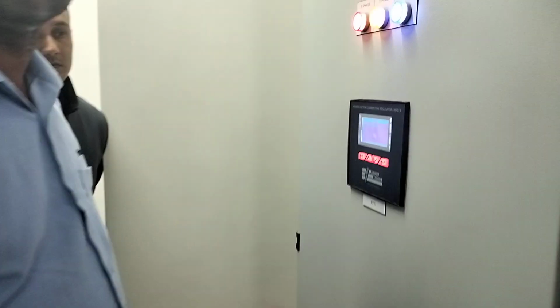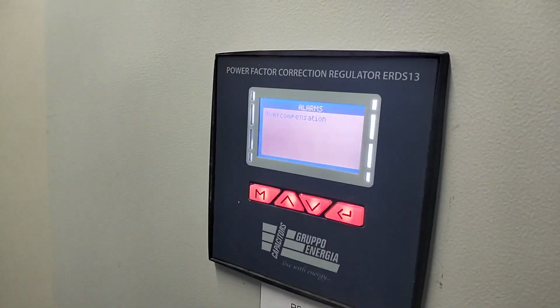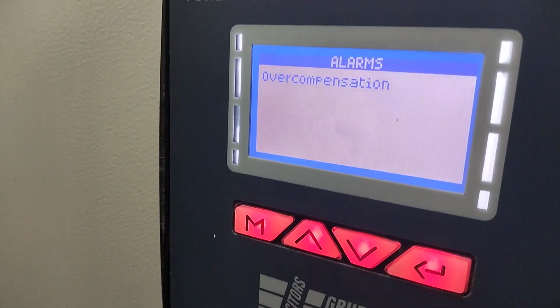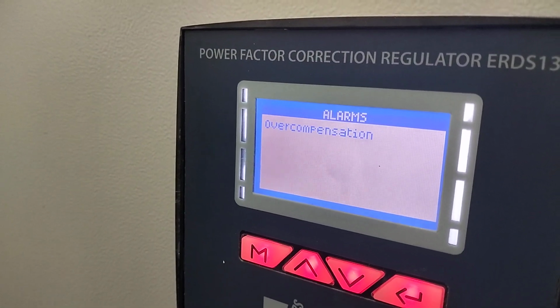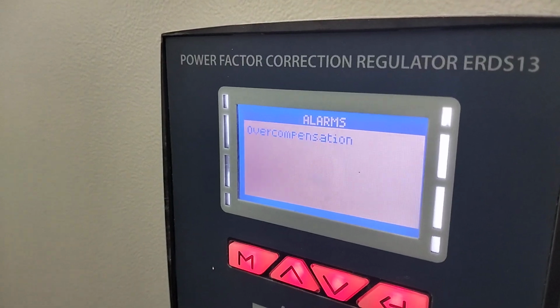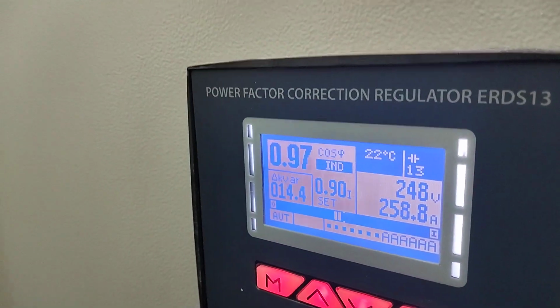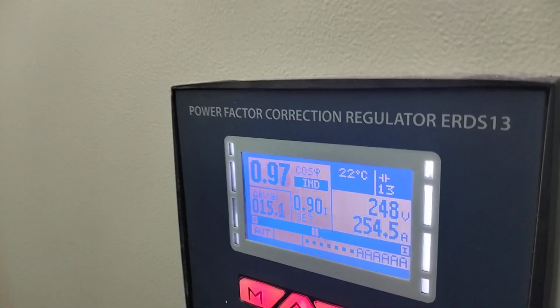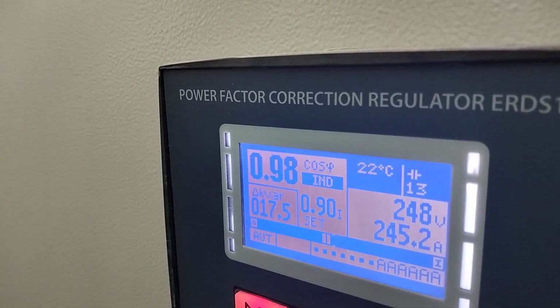Now you can see there is an alarm, overcompensation. Overcompensation means the system is telling it's over. For me it's over because my set is 0.9 but we have more than this, more than capacity. It's inductive. It's okay. Sometimes you can see it's capacitive. Then it means you are connected to some UPS load, some electronics like this.